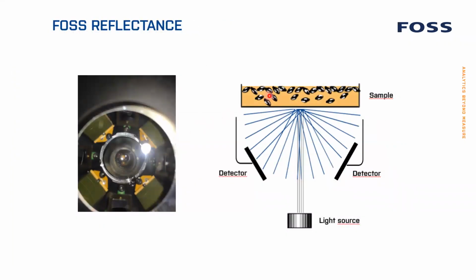So this is how it looks inside a Foss instrument, where you have a sample cup, and a light source coming from the monochromator, so you have one wavelength coming up, hitting the sample, and then it's reflected down on the detectors. This is a picture taken on the instrument where normally the cup is sitting. So this is how it looks when it's open for taking a scan.